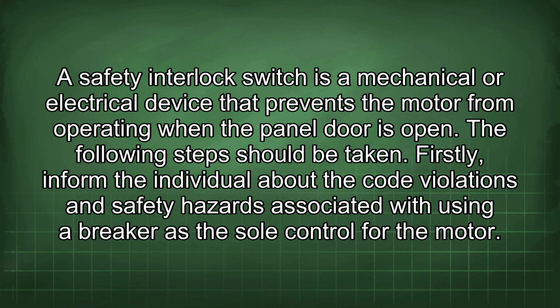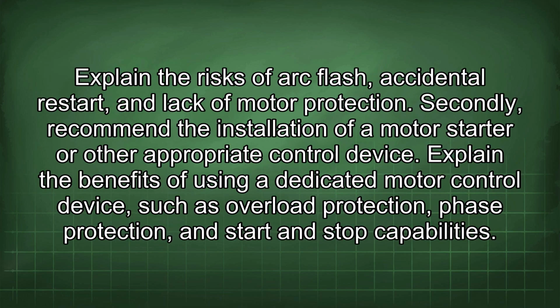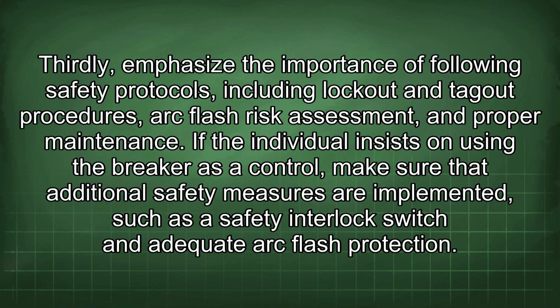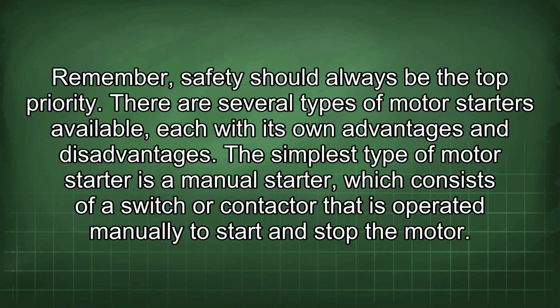The following steps should be taken. Firstly, inform the individual about the code violations and safety hazards associated with using a breaker as the sole control for the motor. Explain the risks of arc flash, accidental restart, and lack of motor protection. Secondly, recommend the installation of a motor starter or other appropriate control device. Explain the benefits of using a dedicated motor control device, such as overload protection, phase protection, and start and stop capabilities. Thirdly, emphasize the importance of following safety protocols, including lockout and tagout procedures, arc flash risk assessment, and proper maintenance. If the individual insists on using the breaker as a control, make sure that additional safety measures are implemented, such as a safety interlock switch and adequate arc flash protection. Remember, safety should always be the top priority.